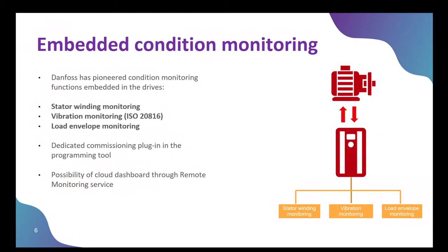Then to be more specific, we have embedded in the drive 3 functions for condition monitoring. And these 3 functions are the monitoring of the stator winding. That means if there is an electrical problem in the winding of the motor, the drive will detect that early, before breakdown. Then we implemented a vibration monitoring that's according to ISO 20816 standard. So any change in looseness, eccentricity will be detected. And then a change of the load, so-called load envelope. That means if, for example, in a water pumping application, you get sand in the pump or the impeller gets worn out, then this change will be detected. This, of course, needs also a dedicated commissioning tool so you can visualize these graphs.